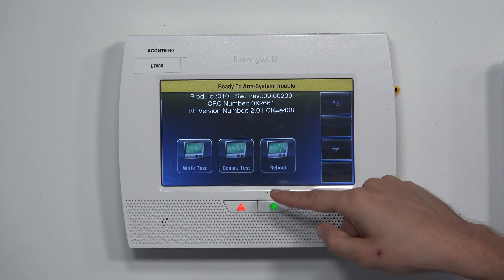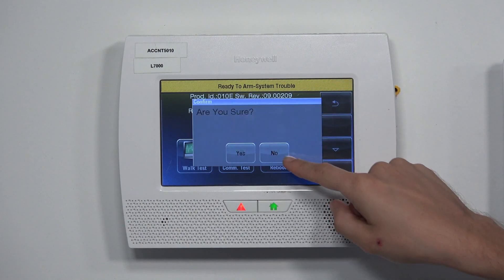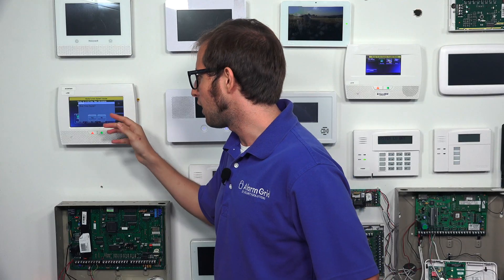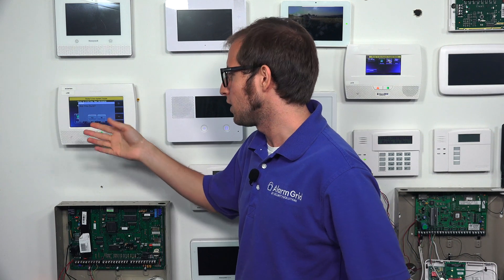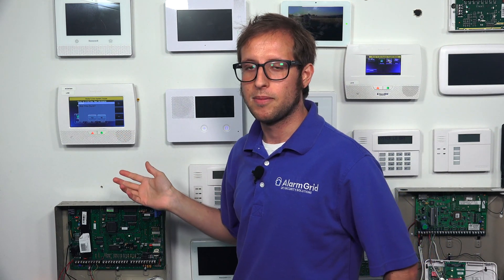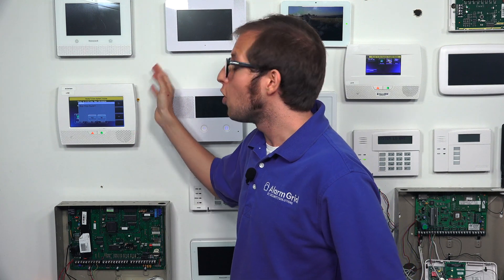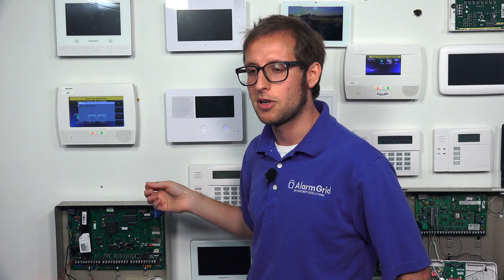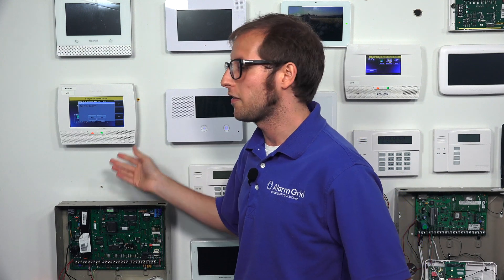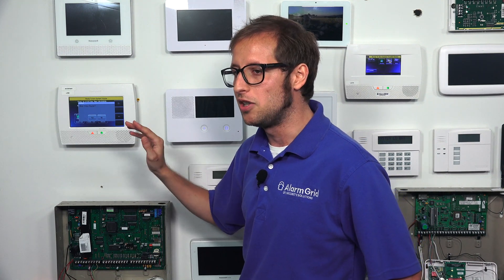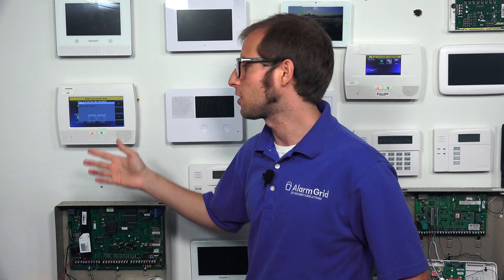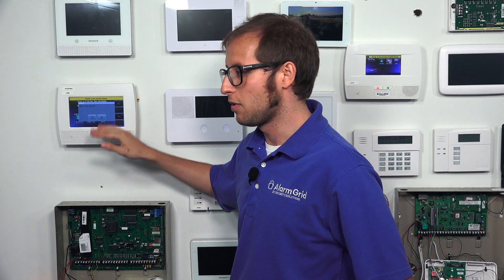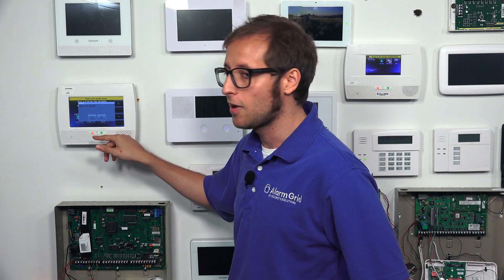We're going to choose Test, then Reboot. It's going to ask if we're sure, and once I click Yes it will begin rebooting. Now, if you don't know the master code for your system, there is another way: you can open up the panel, disconnect the backup battery, and unplug the transformer to power down the system completely. Then when you plug the transformer back in, the system will boot back up. But since we know our master code, we're going to do it this way.